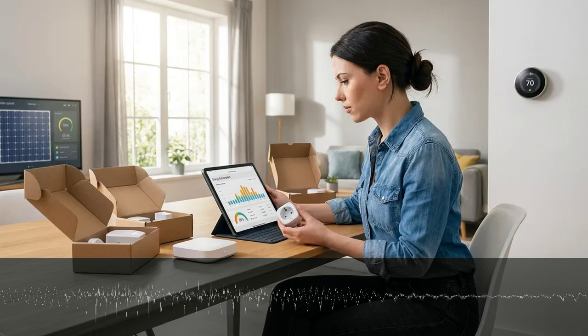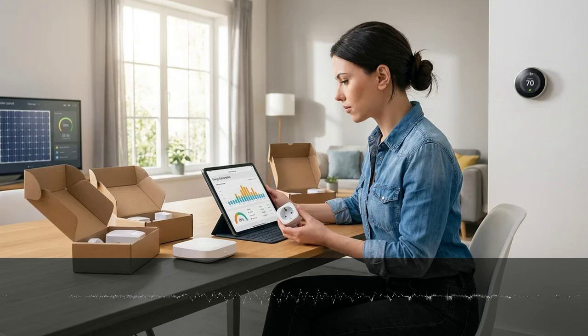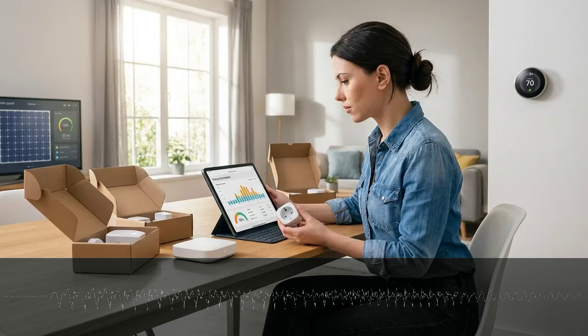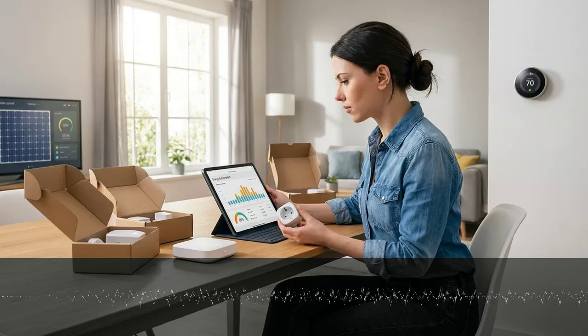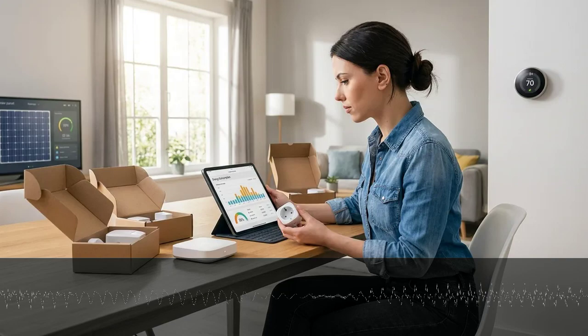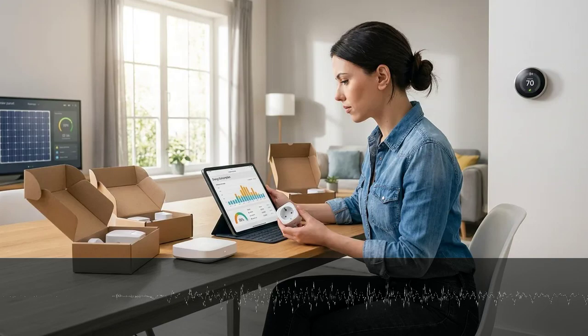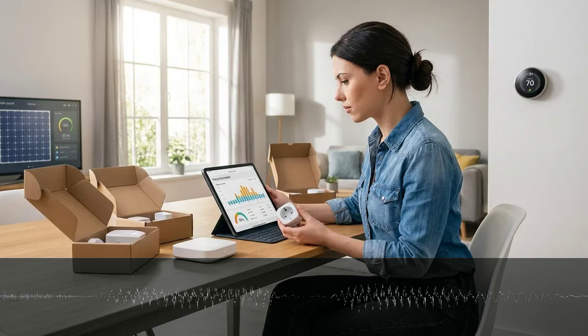You're measuring always-on load, which is the flat baseline when everything's off, typically 200 to 600 watts for vampire draw. You're also measuring peak demand windows during morning and evening HVAC plus cooking, and phantom loads from devices that spike periodically, even when idle. I discovered a malfunctioning dehumidifier drawing 380 watts continuously during my first baseline audit. It should have cycled to 12 watts standby between runs.